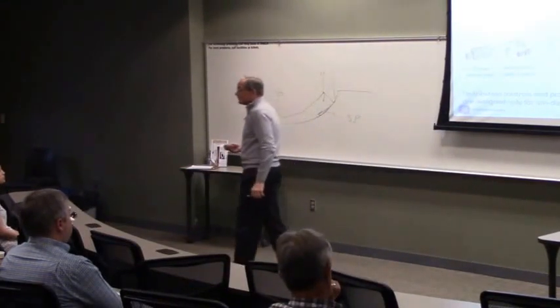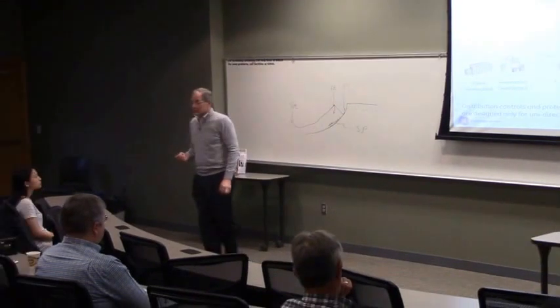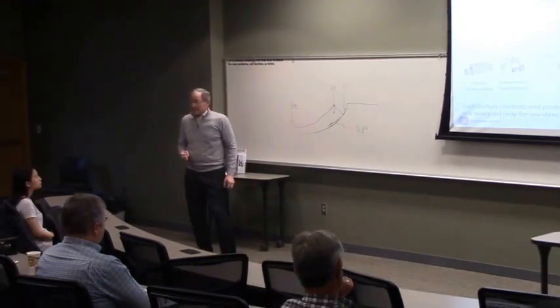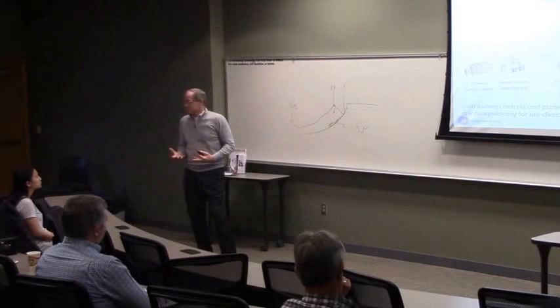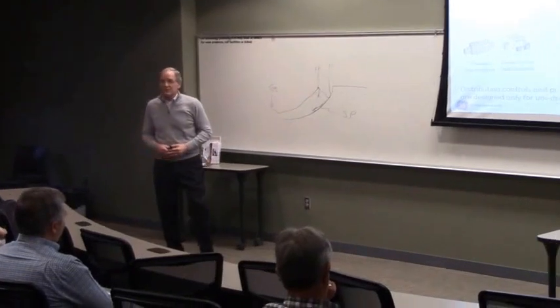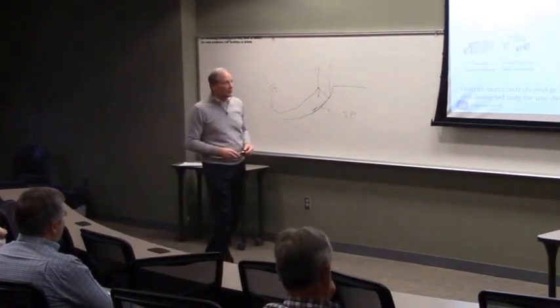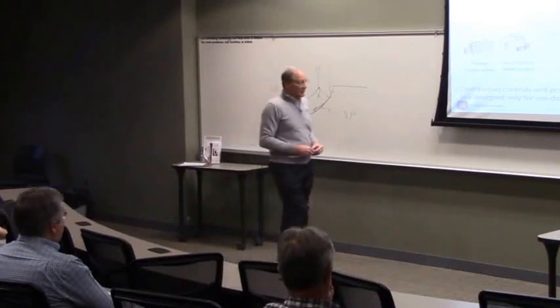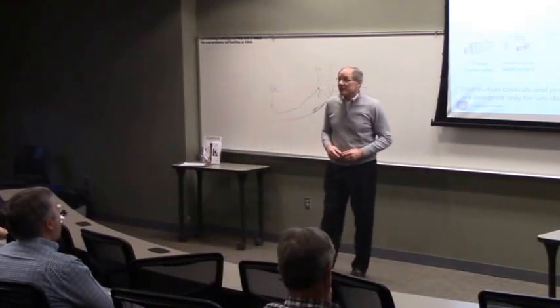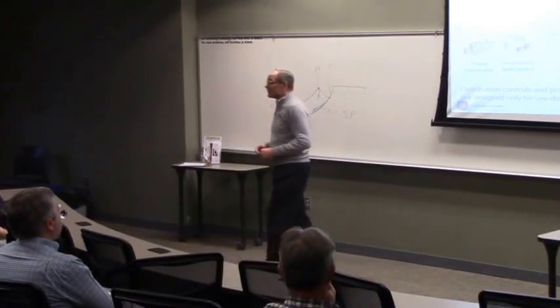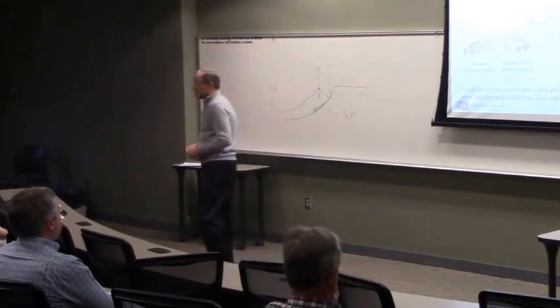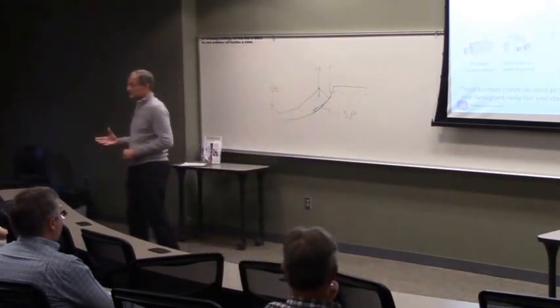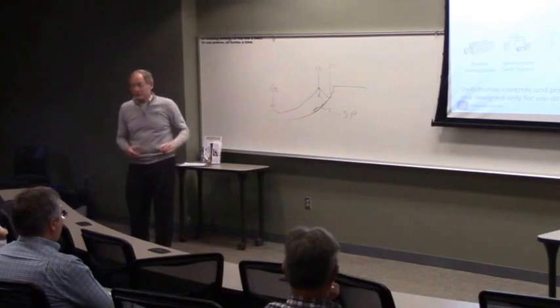And I've got an article I did about 15 years ago that, again, I could send. It was an Omaha Public Power District generator step-up transformer, a Westinghouse shell-form transformer design. It was known to have static electrification problems. And when this started failing, we couldn't de-energize it because it was right outside, too critical.